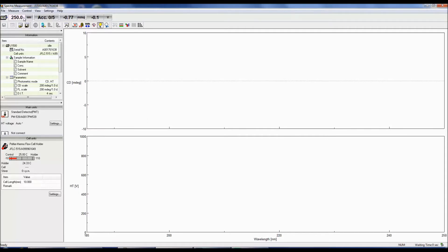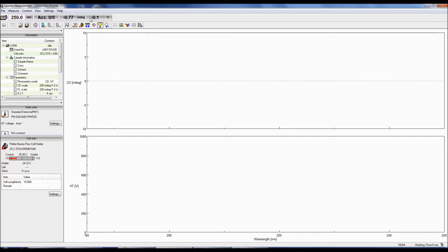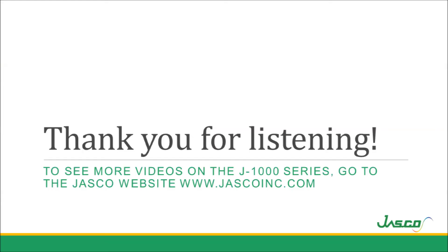At the top of the spectrum measurement, the starting wavelength, number of accumulations, and the values for the photometric modes selected will be displayed. To begin your measurement, make sure your shutter is open and select either baseline or sample measurement icon in the menu bar.